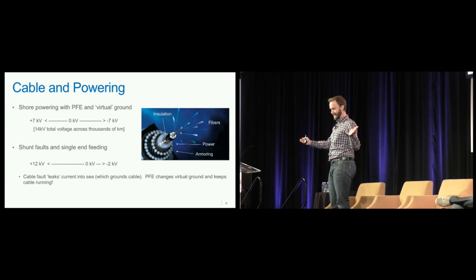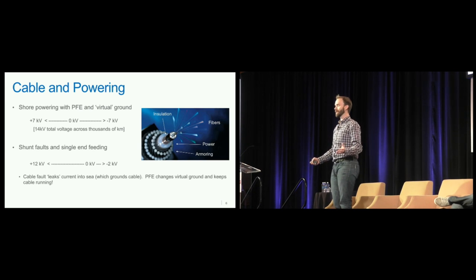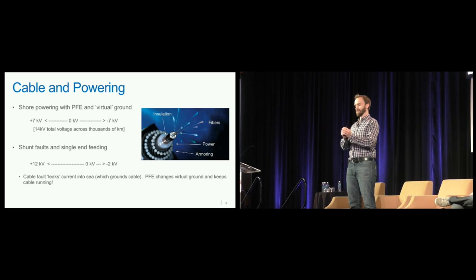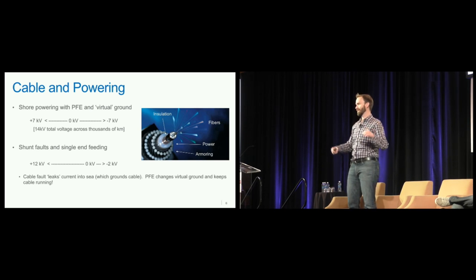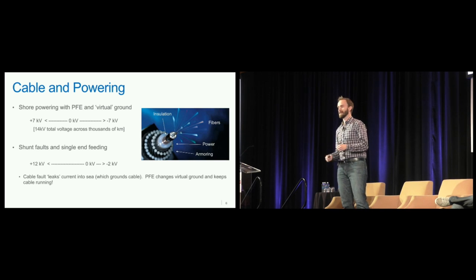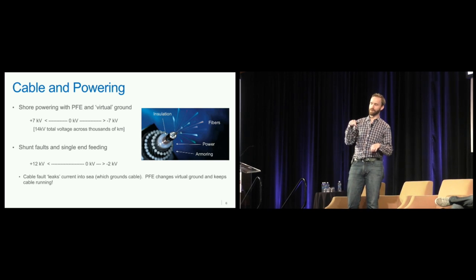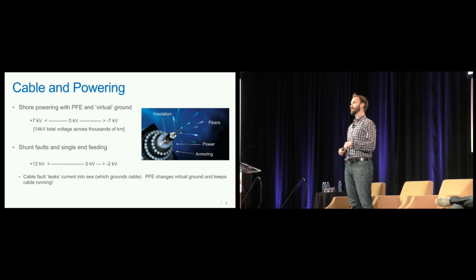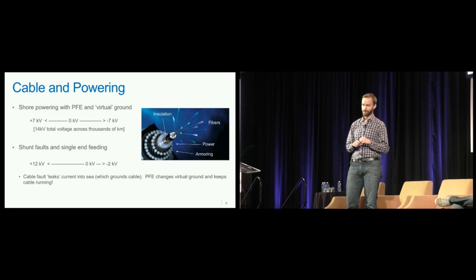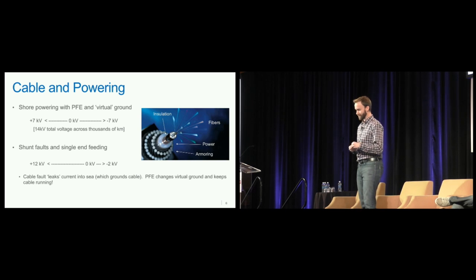You want to design the cable to enable single-end feeding. If the cable is too long, or the power feed equipment doesn't have enough voltage, or you put too many active components like repeaters in the cable, you can't achieve this. More repeaters give better performance but may prevent single-end feeding — so there are real trade-offs in the design.